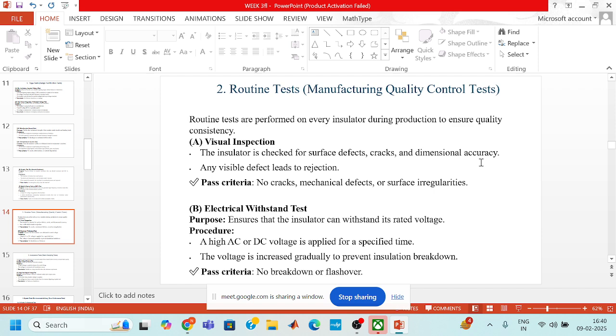Second is the routine test. It is also known as the manufacturing quality control test. These tests are performed on every insulator during production to ensure quality consistency. Under this, there are two categories. First is visual inspection. The insulator is checked for surface defects, cracks, and dimensional accuracy. If there are any visible defects, that can lead to rejection. If there are no cracks, mechanical defects, or surface irregularity, then the insulator will pass the visual inspection test.